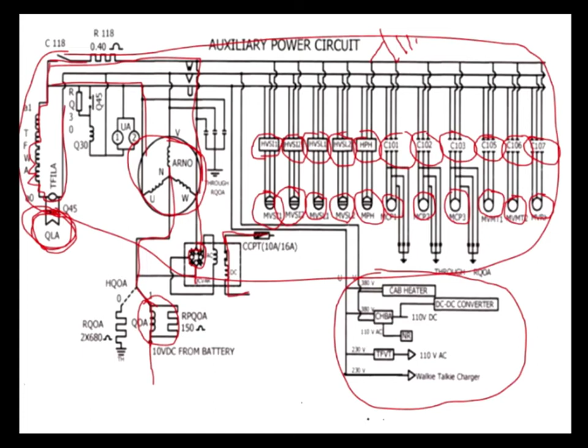In case of any earth fault in the auxiliary power circuit, earth fault means in case any cable of the auxiliary power circuit comes in contact with the loco body and the circuit is completed back to battery negative through HQOA, through loco body, and QoA gets energized. In such case, DJ also trips. On run, if QoA is energized and DJ is tripped, the loco pilot has to troubleshoot like this.